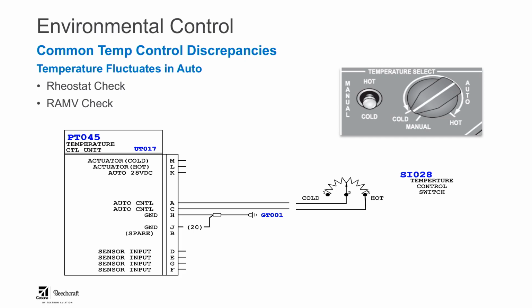And so what we're looking for is there's a limitation on what the cold resistance should be and what the warm resistance should be, and then we want to see a nice smooth linear change. If there's an erratic jump anywhere along that line, I would replace that rheostat, because what can happen is it can get a little sweet spot. Say you run it at 1 o'clock all the time, well, maybe that sweet spot develops around 1 o'clock, and it will vary the resistance.